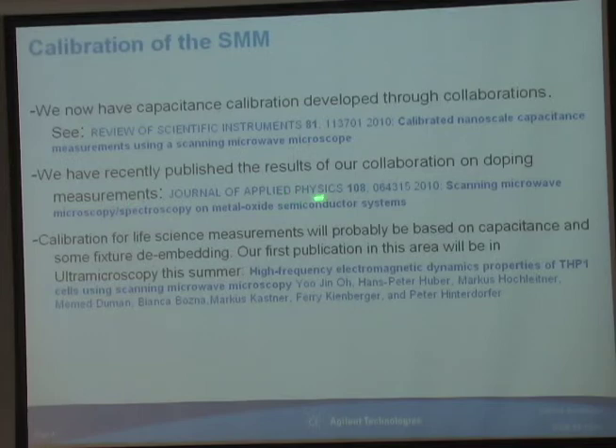We did some collaborations in Europe where we looked into measuring doping. If you think about doping in semiconductors, the more dopant you have, the higher the conductivity, so your capacitance measurement correlates to your doping measurement through that fact. There's a group in Belgium called IMEC that makes a doping standard where they've characterized it chemically, so they know what they're doing, and they give you a sample which has a bunch of different doping values and known geometries. We can use that to calibrate for doping concentration.